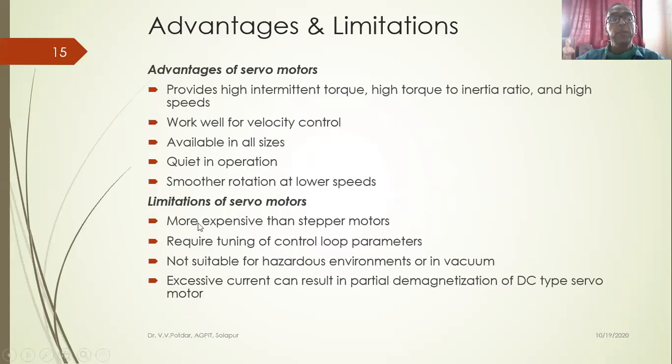Limitations: these are a bit more expensive than stepper motors. They require tuning of control loop parameters. These are not suitable for hazardous environments or in vacuum. Excessive current can result in partial demagnetization of DC type servo motors. So these are a few of the limitations.